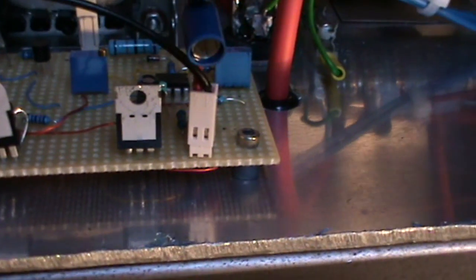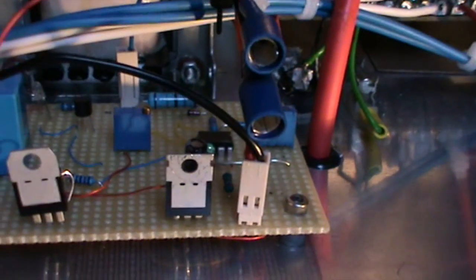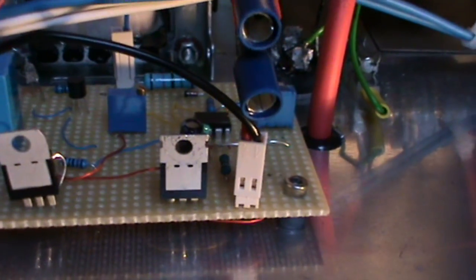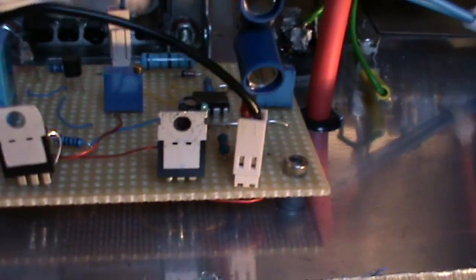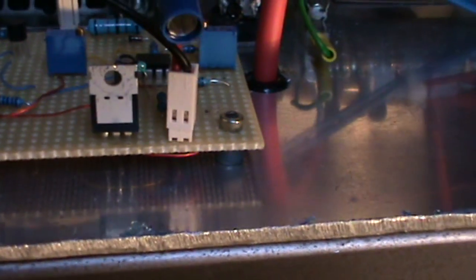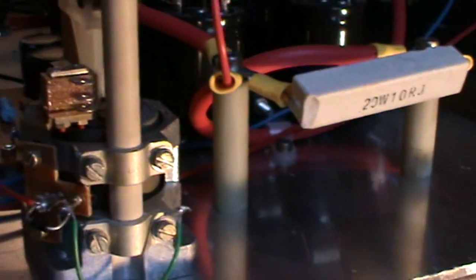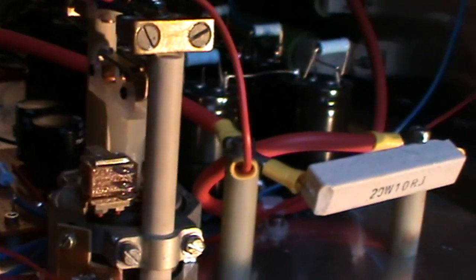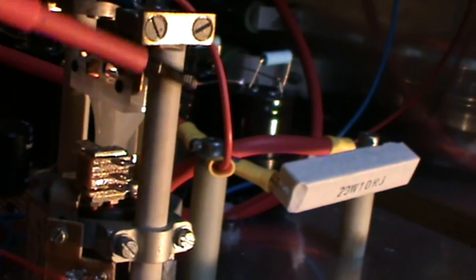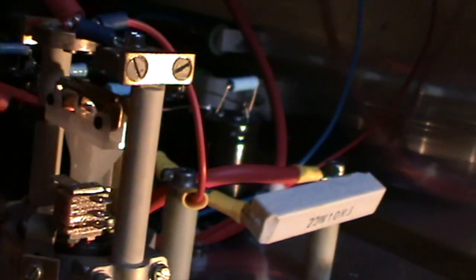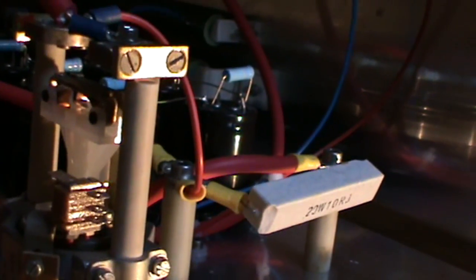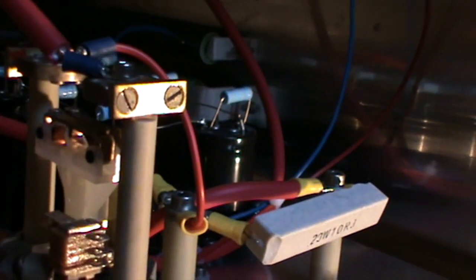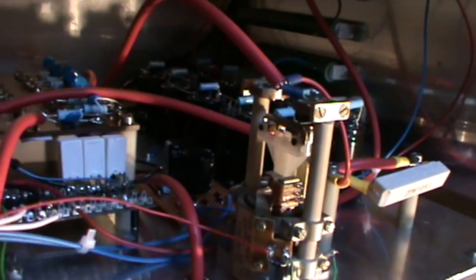The gate of a BS170 MOSFET will then operate the relay. So if the current draw is too excessive, you get an excessive negative voltage, which is converted by the electronics to trip the main relay. That's the secondary relay, which operates this big high voltage relay here, on insulating porcelain or ceramic stands, which could then trip the HT.